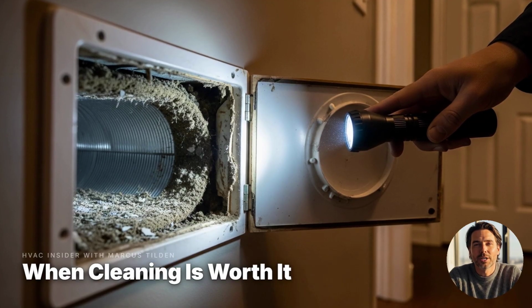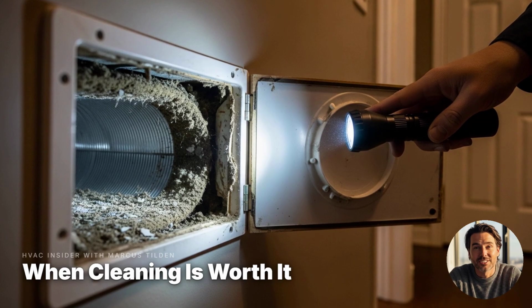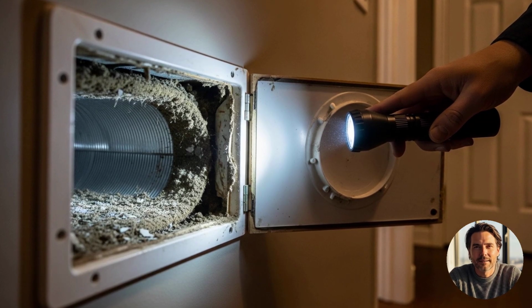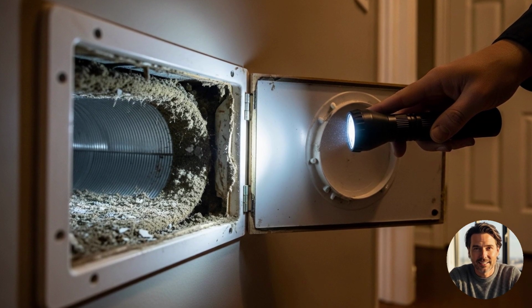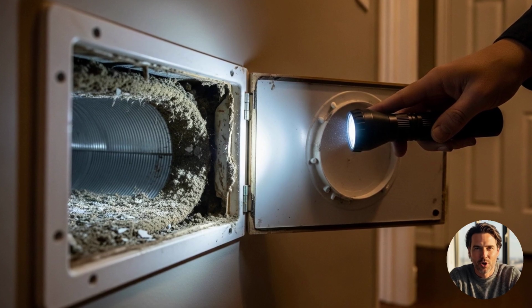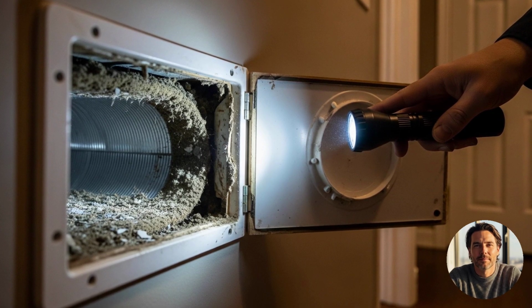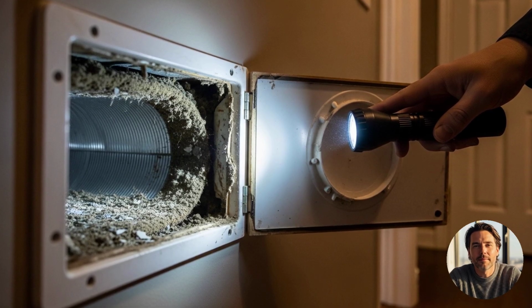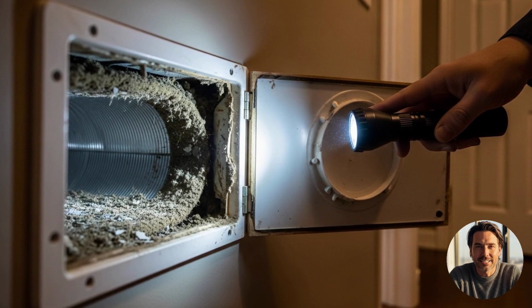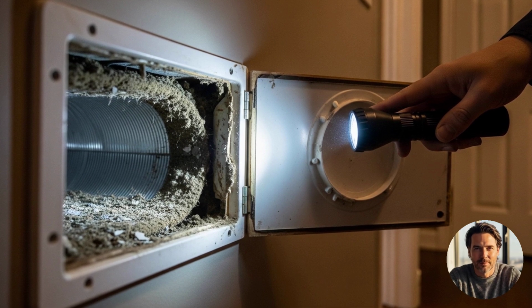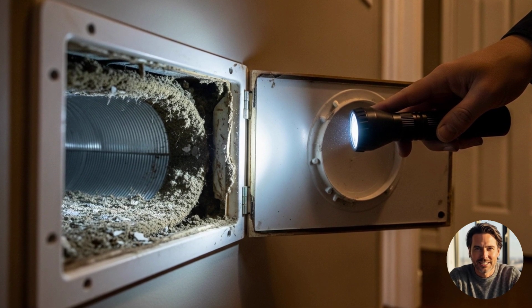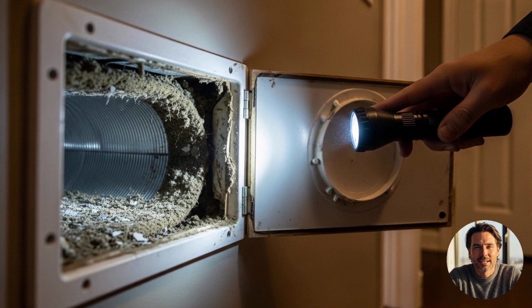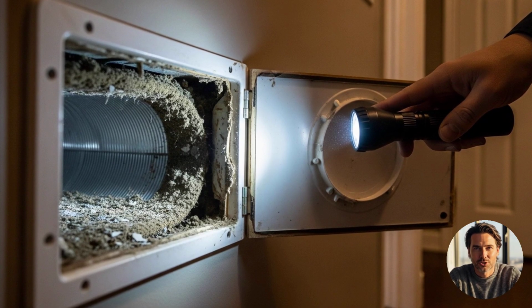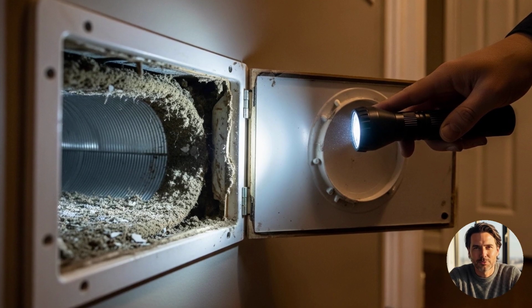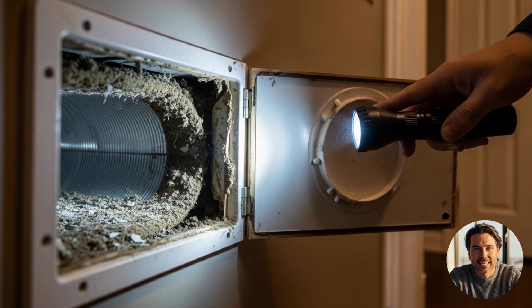That does not mean duct cleaning is always a scam. There are real reasons to do it. If you have visible mold growing inside the ducts, if rodents or insects have gotten in, or if a renovation dumped drywall dust through the whole system, cleaning is the right call. The rule is simple: clean ducts when something is actually in them, not on a schedule a salesman invented. If you do not understand it, you cannot push back on it. So let us understand it. Ask them to show you the problem before you pay to solve it.